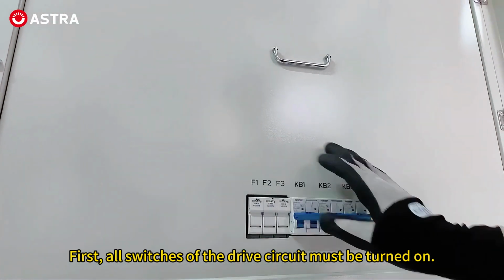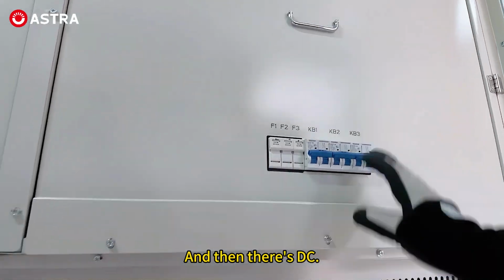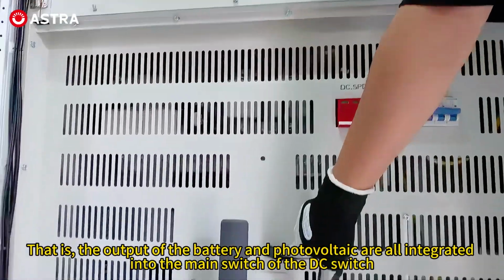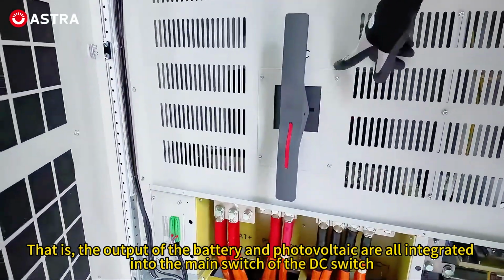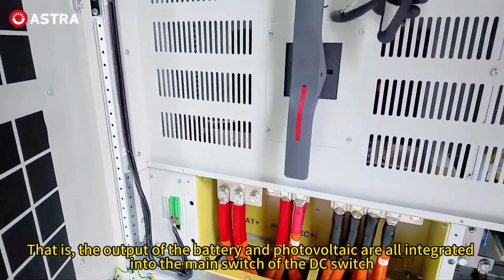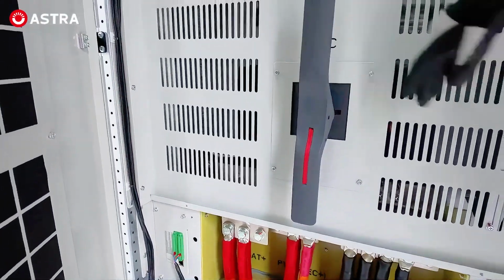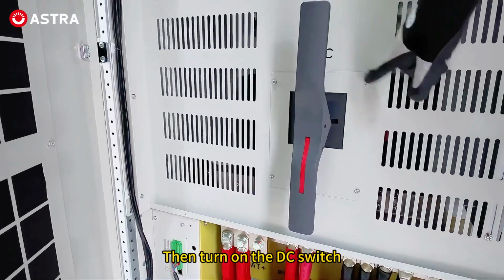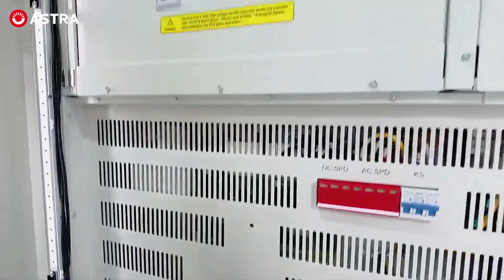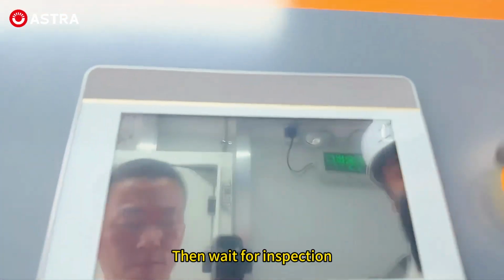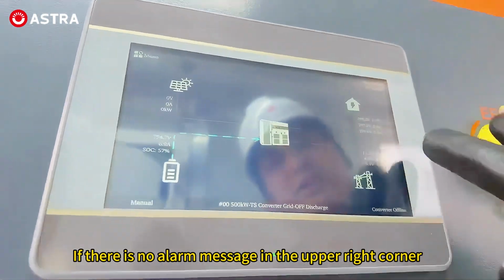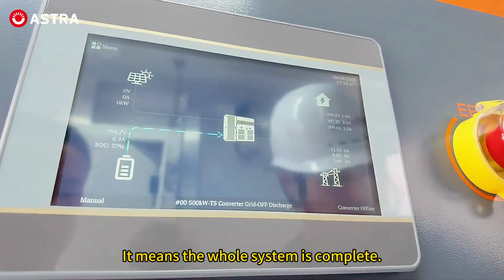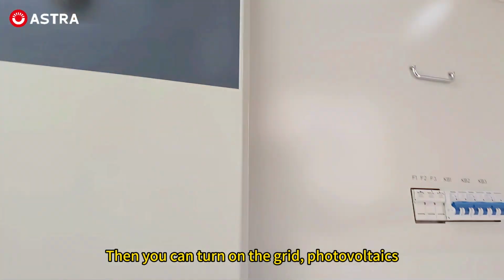First, all switches of the drive circuit must be turned on, and then there's DC. That is, the output of the battery and photovoltaic are all integrated into the main switch of the DC switch. Then turn on the DC switch. The whole screen will light up. Then wait for inspection. If there is no alarm message in the upper right corner, it means the whole system is complete. Then you can turn on the grid, photovoltaics.